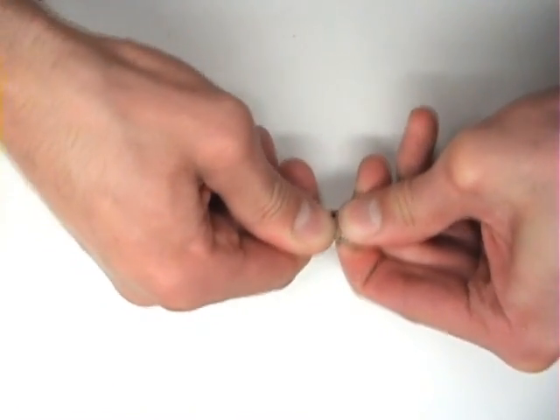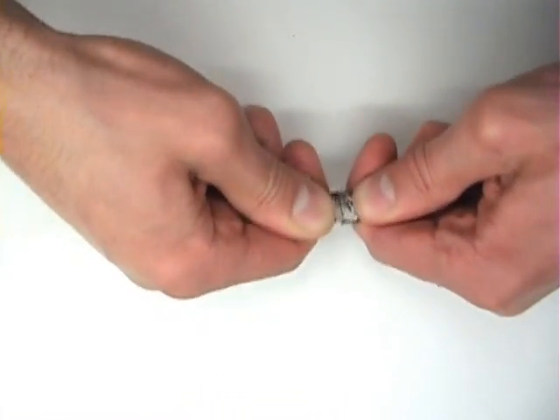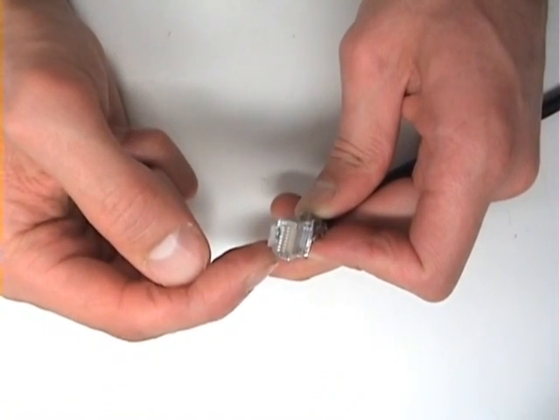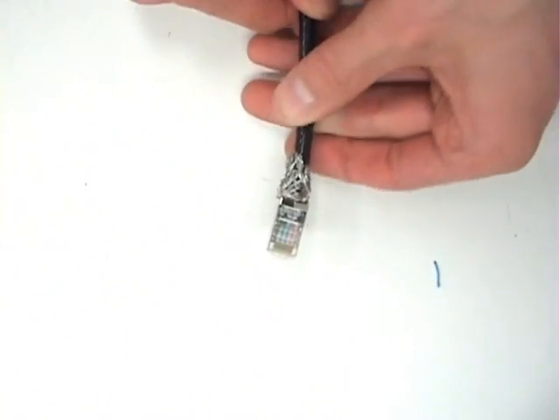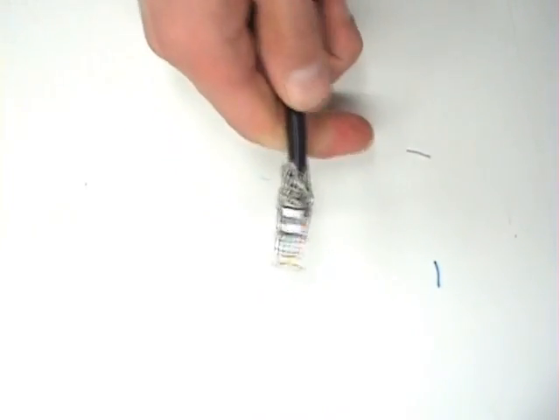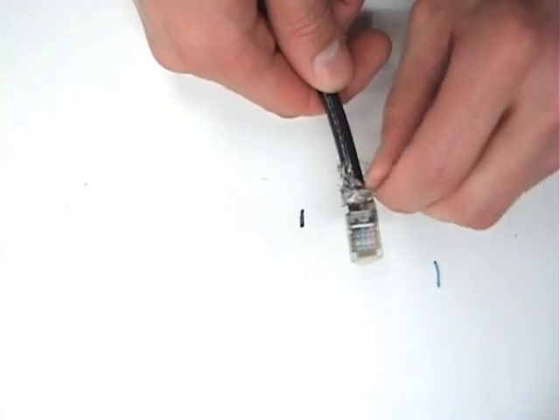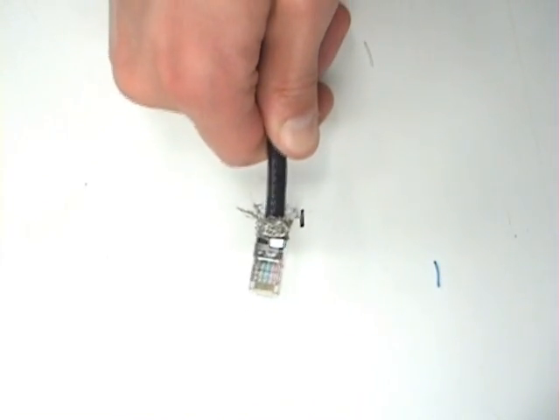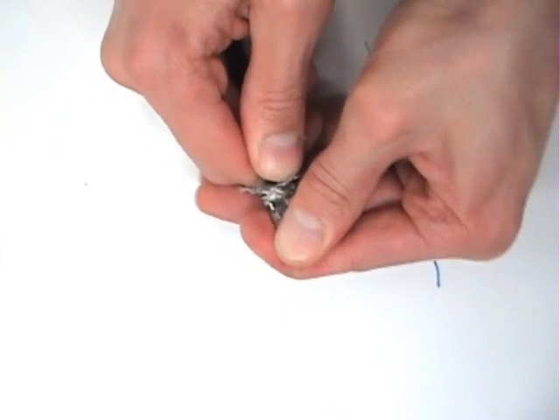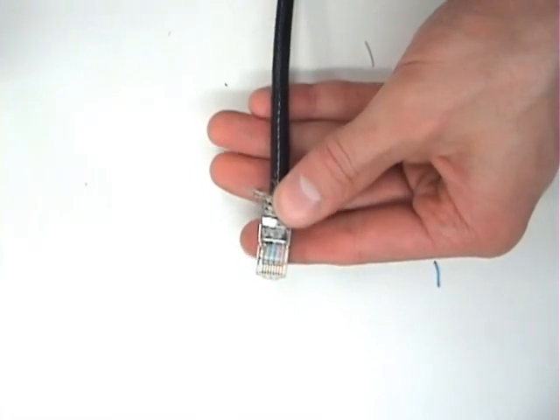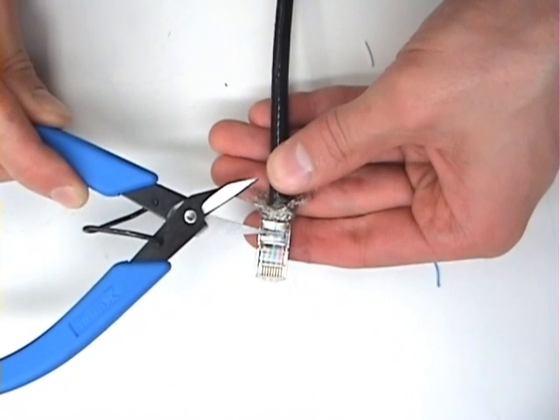Once you feel that the wires are fully inserted, ensure that you can see the copper tips of all the wires at the top of the connector. Now, if you were unable to insert enough jacket into the connector in order to fill the crimp window, you can stretch more jacket towards the connector and then work more jacket inside to fill the window. And now, there is enough jacket in the window to make a reliable crimp.